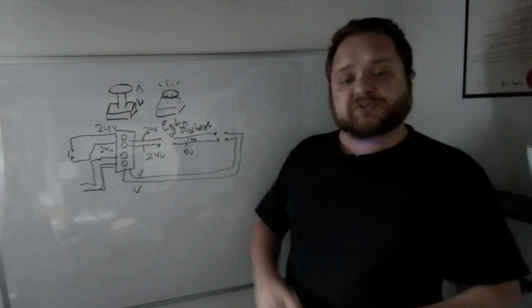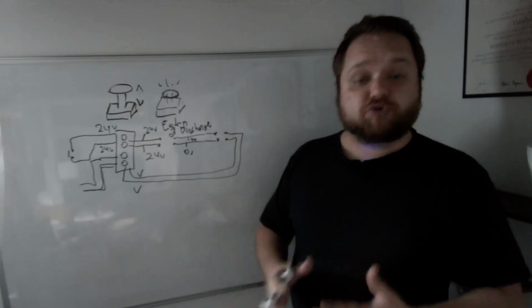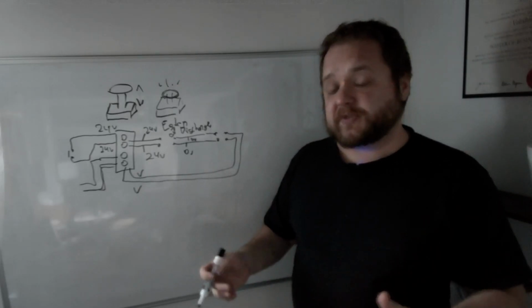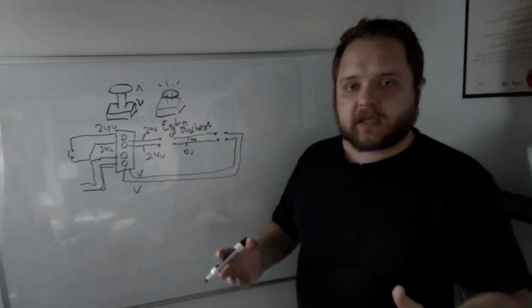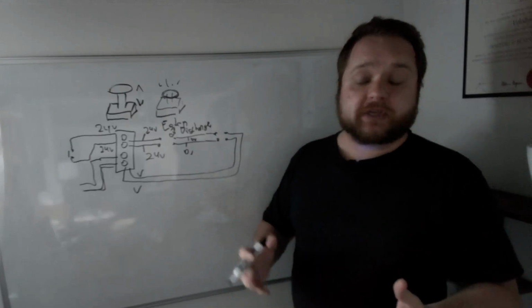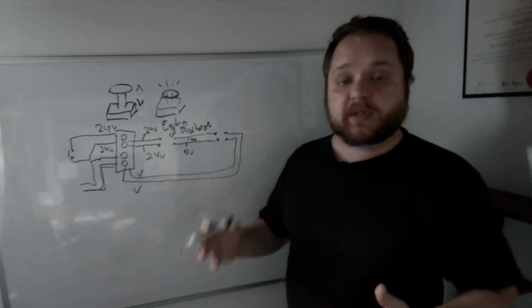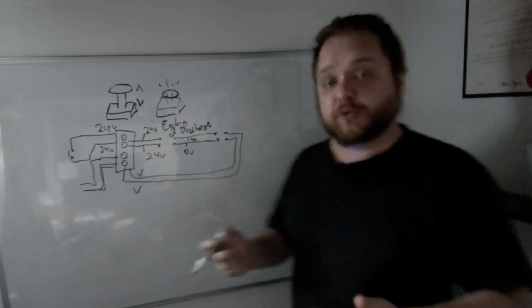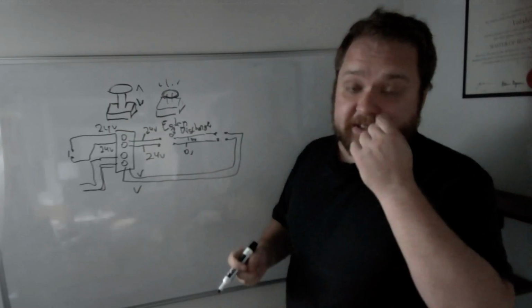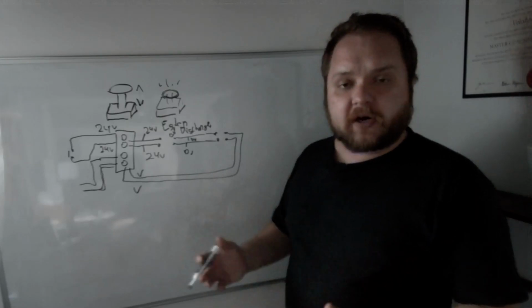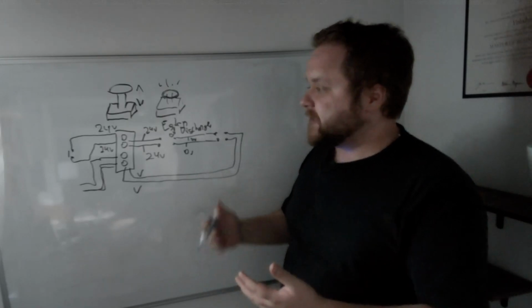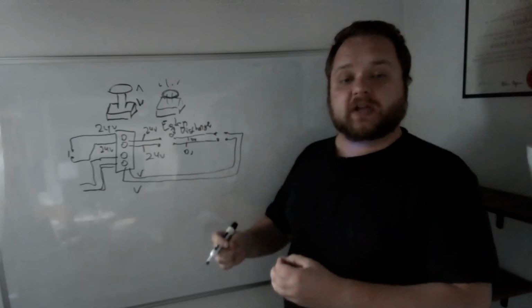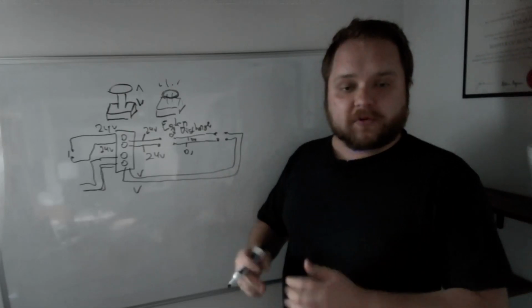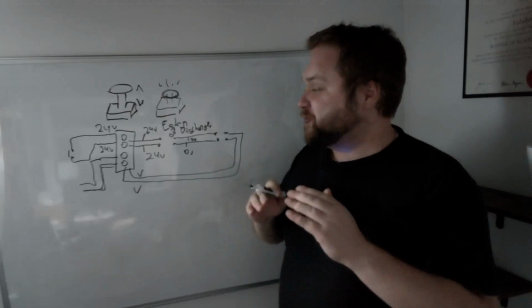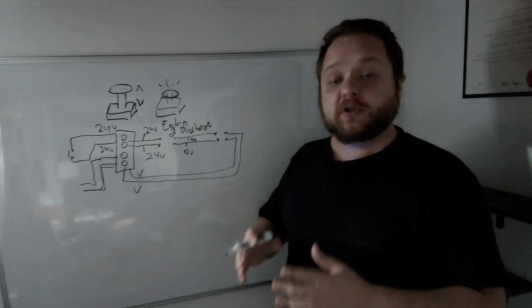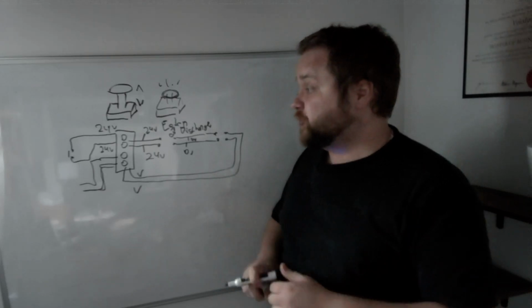So in some very extreme cases, you need to bypass safety circuits. And this is not something I would recommend lightly. This is not something you should engage in if you don't have full responsibility, full control, full understanding of what you're doing. But in certain instances, during, for example, commissioning or startup, you need to be able to bypass a certain feature in order to understand where the failure points are. And of course, as I've mentioned a couple of times, you need to make sure that no personnel is present. Only the ones that understand the risks of doing so are present.